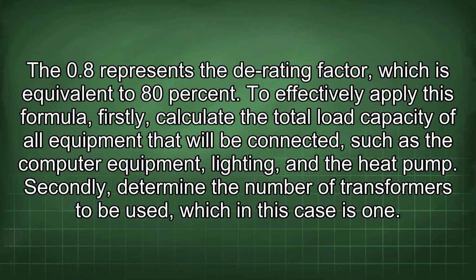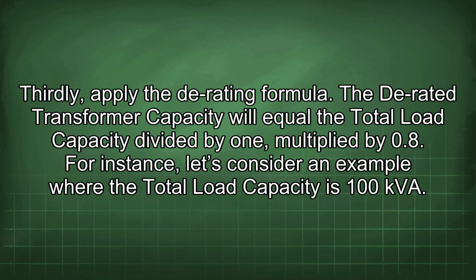To effectively apply this formula, firstly, calculate the total load capacity of all equipment that will be connected, such as the computer equipment, lighting, and the heat pump. Secondly, determine the number of transformers to be used, which in this case is 1. Thirdly, apply the derating formula. The derated transformer capacity will equal the total load capacity divided by 1 multiplied by 0.8.